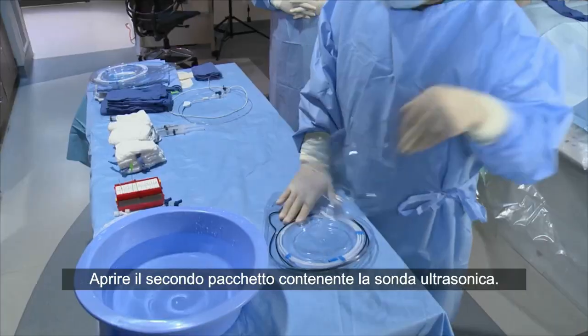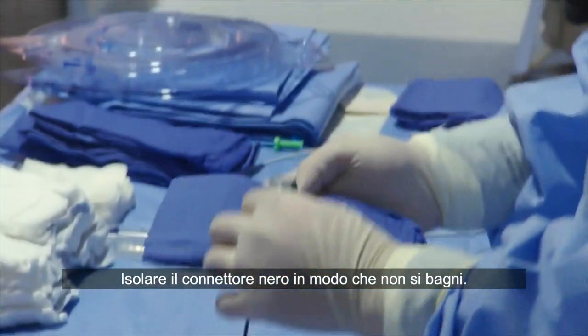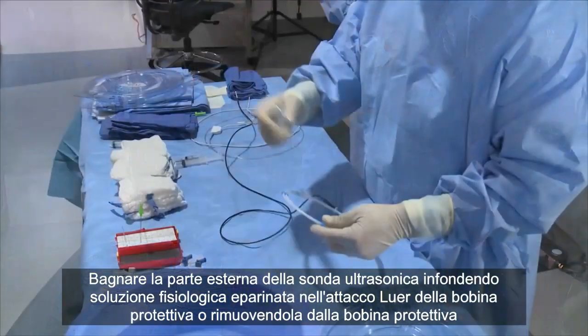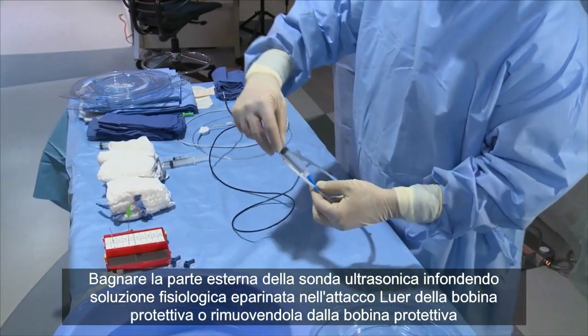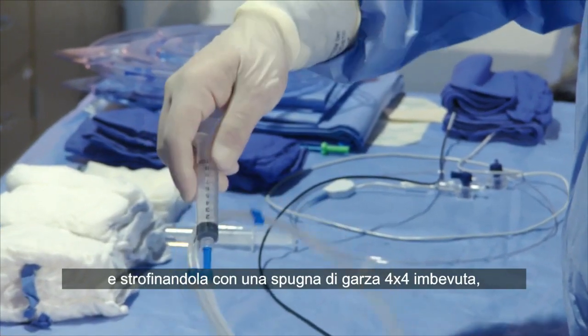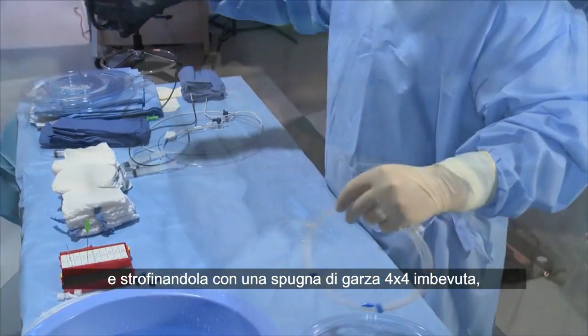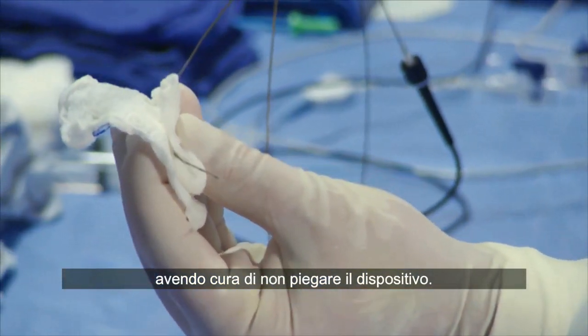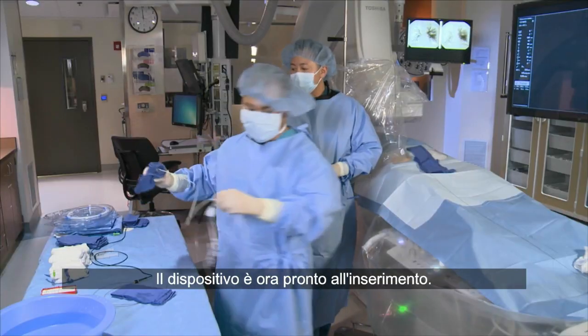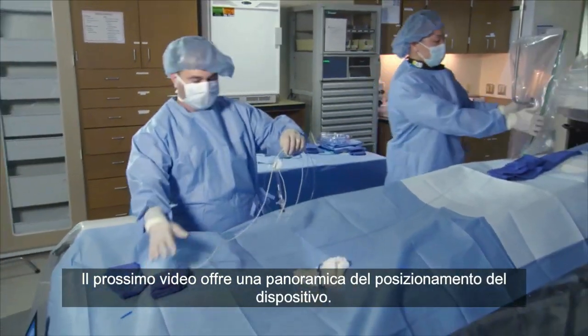Open the second package containing the ultrasonic core. Isolate the black connector so it doesn't get wet. Moisten the outside of the ultrasonic core by either infusing heparinized saline into the luer fitting of the protective coil, or remove it from the protective coil and wipe it with a wet 4x4 gauze sponge, taking care to avoid kinking the device. The device is now ready for insertion. The next video is an overview of device placement.